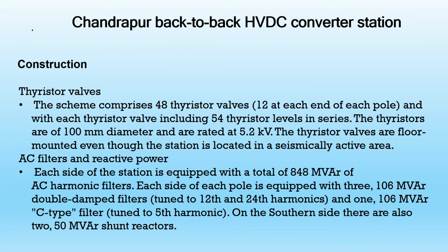The scheme comprises 48 thyristor valves, with each thyristor valve including 54 thyristor levels in series. The thyristors are of 100 mm diameter and are rated at 5.2 kV. The thyristor valves are floor mounted, even though the station is located in a seismically active area.